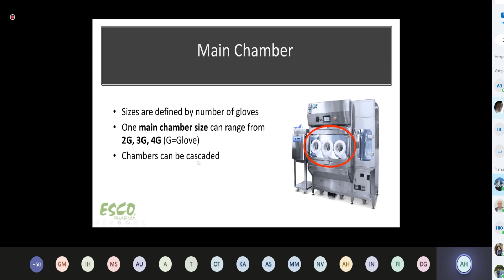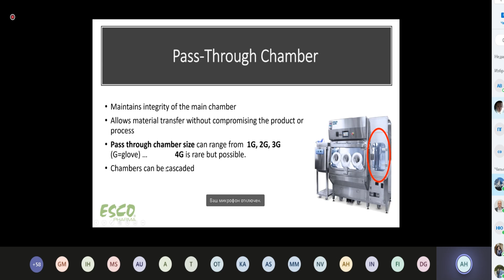For the pass-through chamber, again, you can have different sizes. The pass chamber is very important to protect the main chamber. Normally, 1 glove is very common. 2 glove is also okay. 3 glove is very, very rare, but possible. Sometimes the pass-through chamber can also be very big, like 4 glove. Again, the chambers can be cascaded, that means joined together.